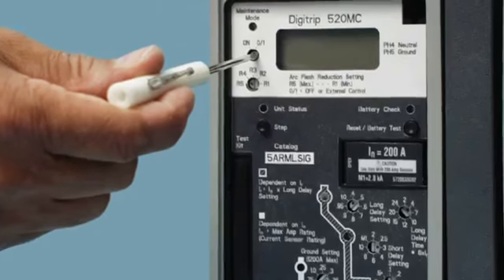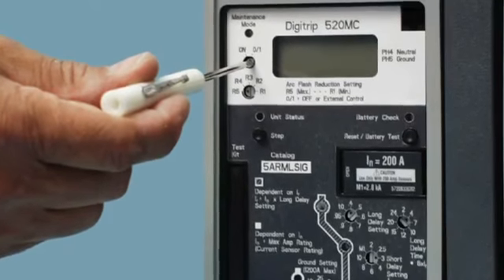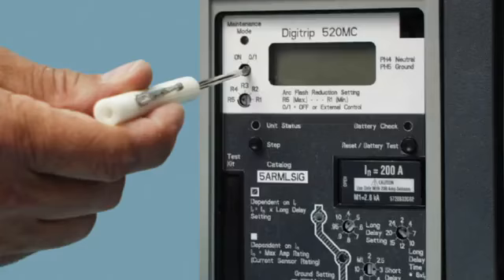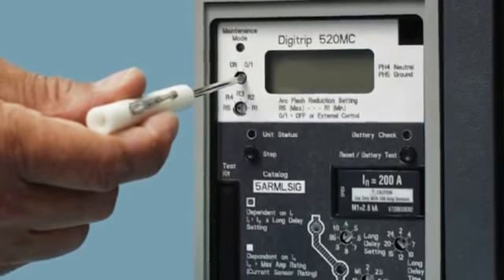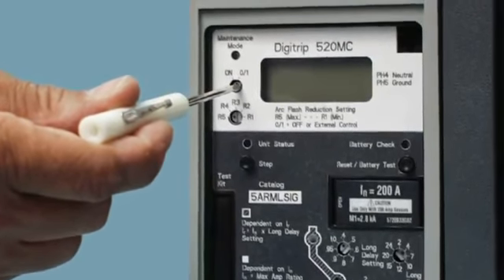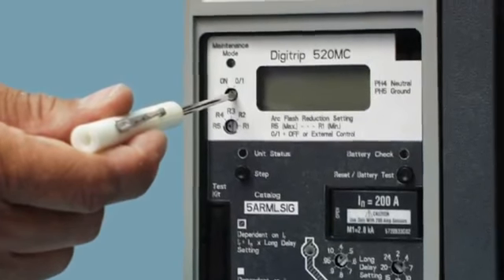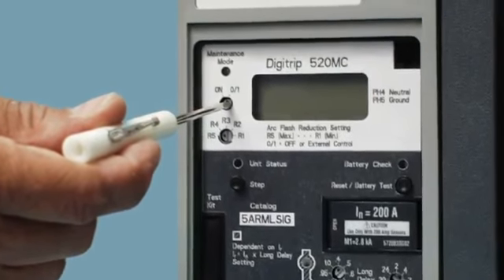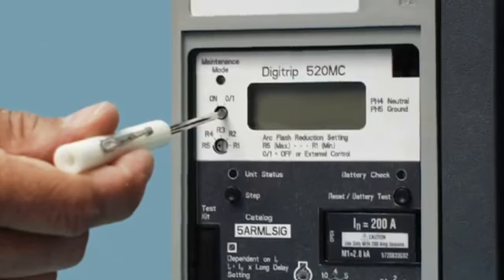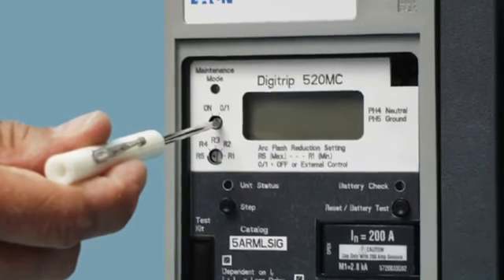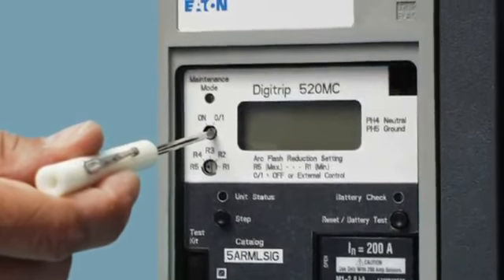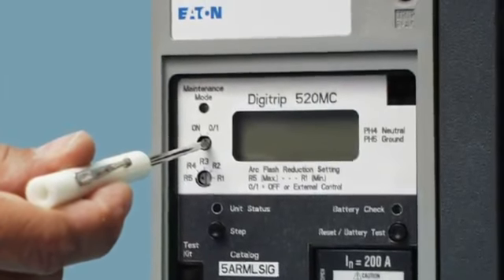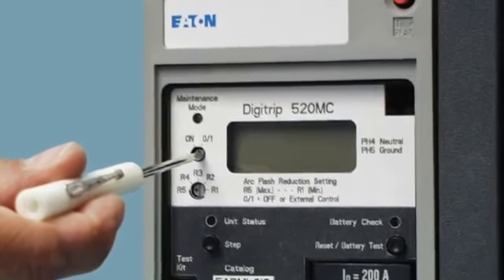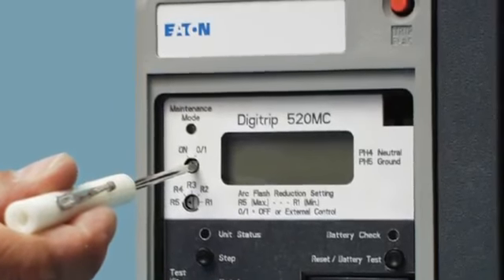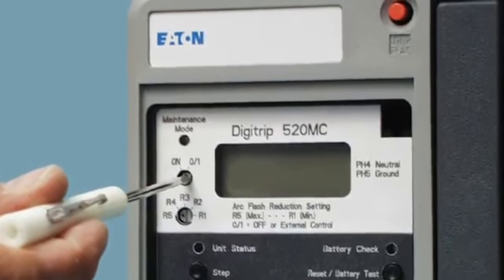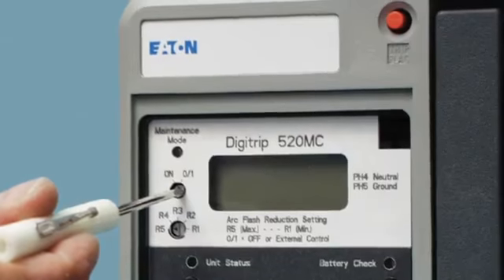ARMS is an optional plug-in module applied to the main breaker that permits the operator to add an instantaneous trip setting to temporarily reduce the breaker's normal trip threshold while performing routine maintenance operations. If the breaker is in this setting, it will open much quicker when an arc fault occurs. By clearing an arc fault faster and limiting its impact on downstream circuits, the ARMS system can greatly reduce the level of energy available during an arc flash event.